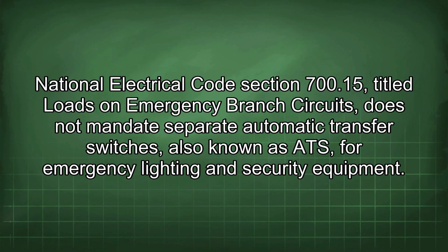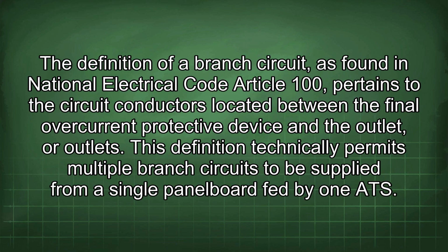National Electrical Code Section 700.15, titled Loads on Emergency Branch Circuits, does not mandate separate automatic transfer switches, also known as ATS, for emergency lighting and security equipment. The definition of a branch circuit, as found in National Electrical Code Article 100, pertains to the circuit conductors located between the final overcurrent protective device and the outlet, or outlets. This definition technically permits multiple branch circuits to be supplied from a single panel board fed by one ATS.